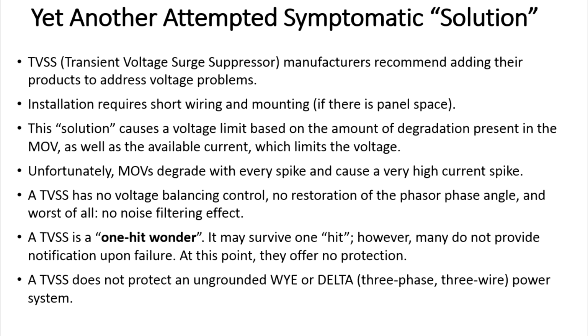The transient voltage surge suppressor is a device that uses a nonlinear component called a metal oxide varistor. As the voltage goes up, its resistance goes down. So the higher the voltage, the more current it will draw. What they do is, as there is a voltage spike, it will convert it to a high current spike, and a spike of a couple thousand volts may be converted to a 10, 20, or 50,000 amp spike in current.